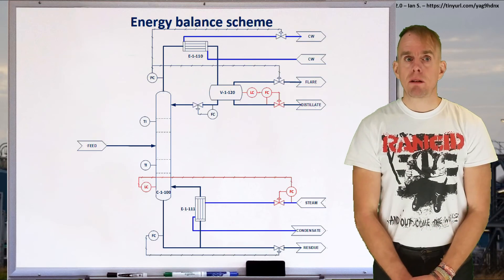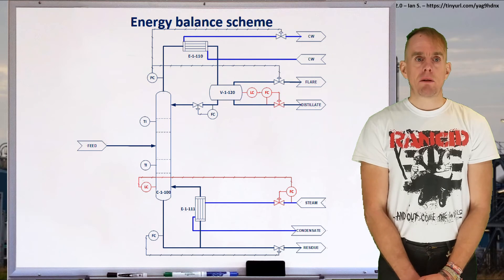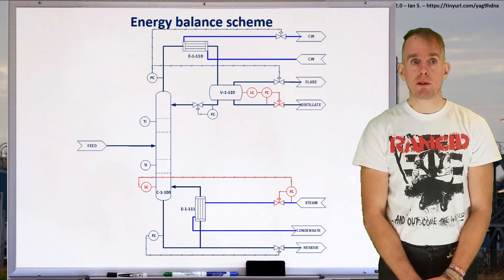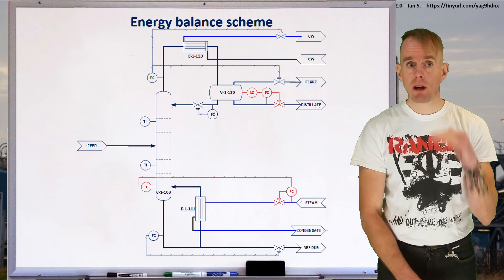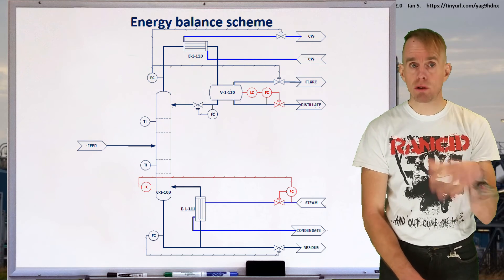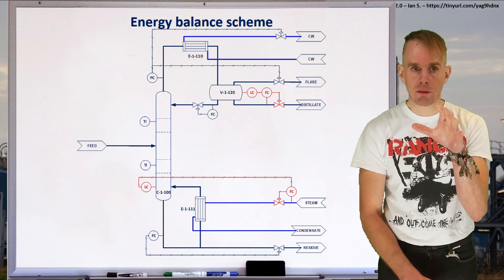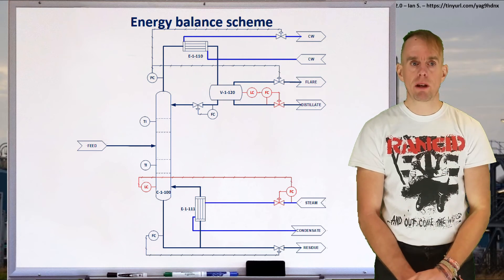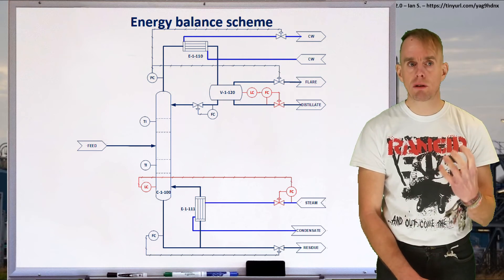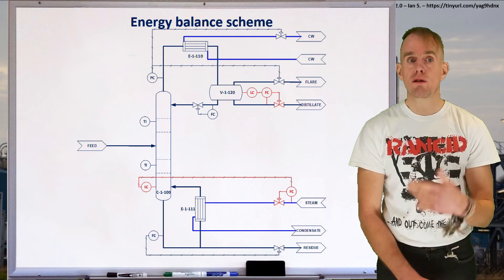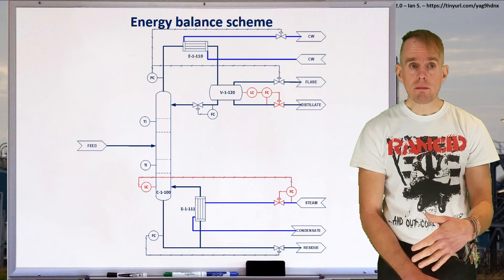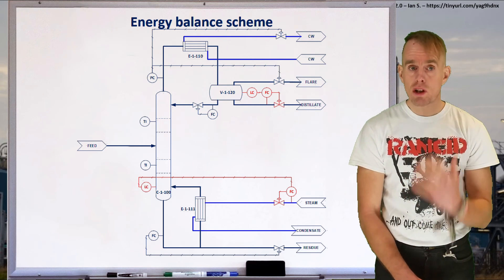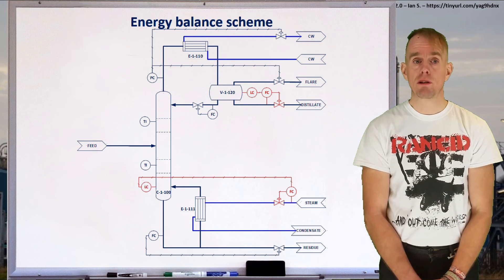Let's illustrate a simple energy balance scheme. The top of the column is unchanged from the previous material balance scheme — we've got level control on the reflux drum cascading onto the flow control to the distillate leaving the process. What we've changed is we've put energy balance control on the base of the column. The level controller for the sump now cascades onto the flow control of the steam into the reboiler. So if we wish to remove more material from the system, we change that steam flow rate to allow us to do that.